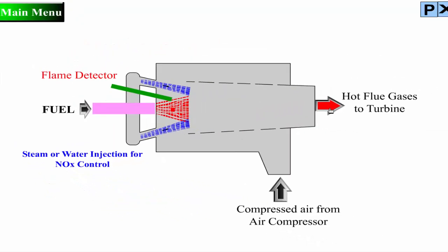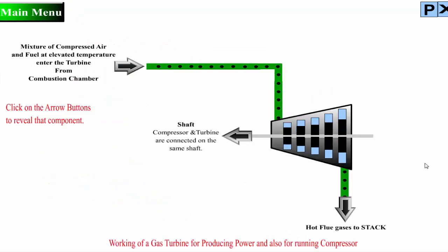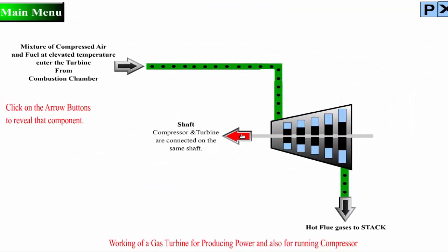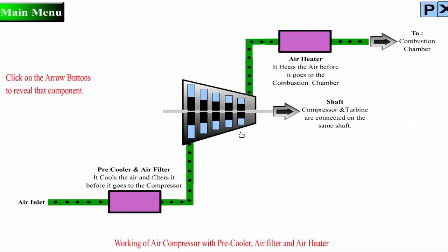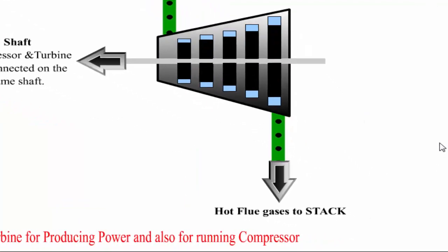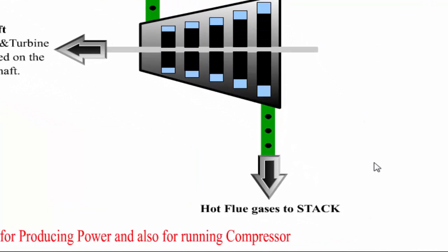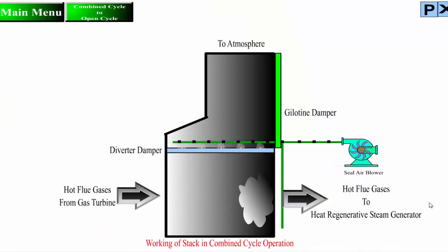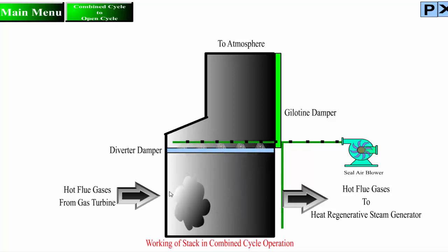One key to a turbine's fuel-to-power efficiency is the temperature at which it operates. Higher temperatures generally mean higher efficiencies, which in turn can lead to more economical operation. Gas flowing through a typical power plant turbine can be as hot as 2,300 degrees Fahrenheit, but some of the critical metals in the turbine can withstand temperatures only as hot as 1,500 to 1,700 degrees Fahrenheit. Therefore, air from the compressor might be used for cooling key turbine components, reducing ultimate thermal efficiency.